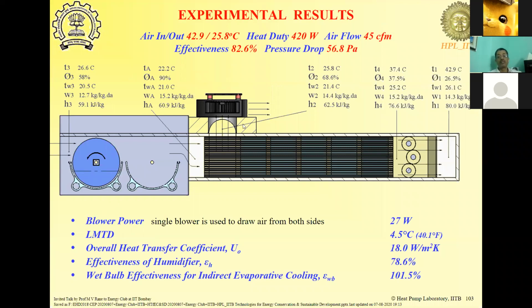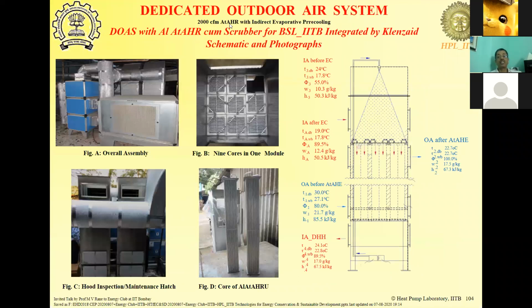This is one of the units which is deployed in the Biosciences Department, Bioschool. It's a 2,000 CFM air-to-air heat recovery indirect evaporative cooler. In this case, the stale air coming out, which is to be exhausted, is sprayed with water. So the 24-degree, 55% indoor air, which is to be exhausted after it has been used, is sprayed with water. The temperature falls down to 19 degrees. So it is essentially getting scrubbed with water, and the temperature drops to 19 degrees.